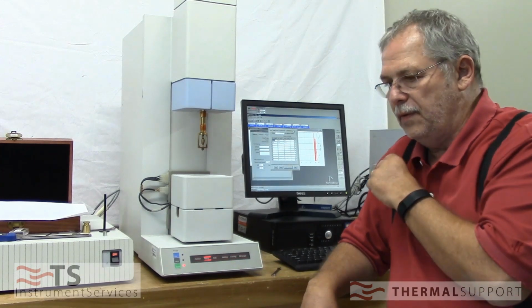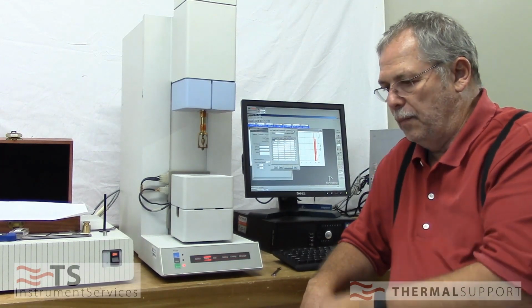It's going to go from 50 to 250. You do not need to change that range because it's extremely linear. I have done them 50 to 250 and immersed the thing in liquid nitrogen, and it'd be dead on afterwards. So depending upon how you're trying to calibrate these things, if you have any sort of trouble, feel free to call. I mean, phone calls are free. We're in the office. We're happy to help you out.